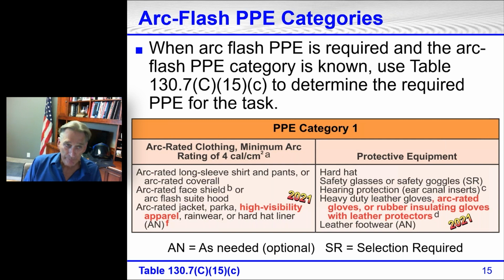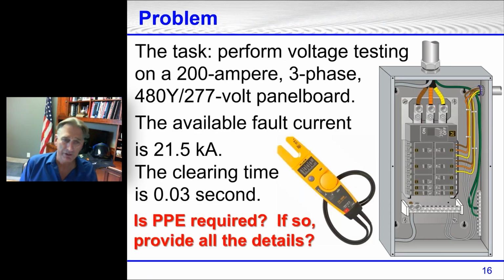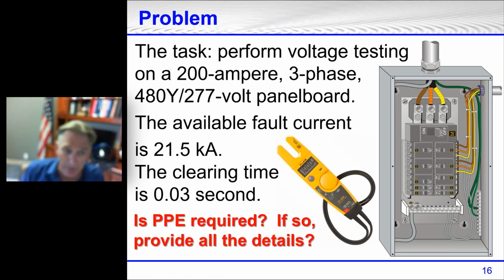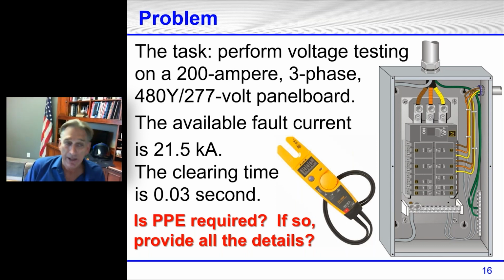And all right, so let's work a problem. Let's do one of the problems here. The task is to perform voltage testing on a 200 ampere 3-phase 480Y/277 volt panel board. The available fault current I'm giving you is 21.5 kA. The clearing time is 0.03 second.